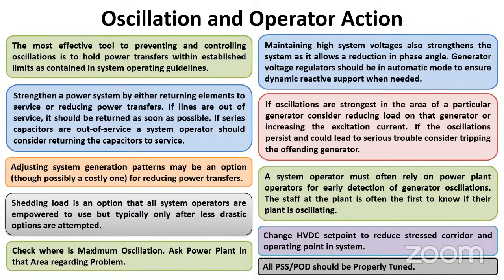That's on the side of the transient stability issue. On the small signal stability aspect, if there is a large power swing, that means it is an inter-area kind of scenario. Inter-area oscillation means the entire system is divided into two parts, and that's one of the major challenges.